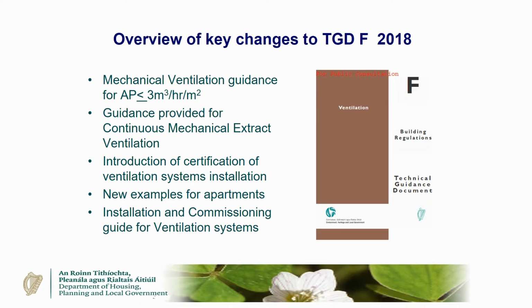We're proposing to introduce a certification scheme for ventilation systems when they're installed. So the installer will install the mechanical ventilation system, he will commission it, and then we'll have a third party, like possibly the air tightness testers, or a scheme running in parallel with the air tightness testers, where a competent third party will come in and validate the ventilation flow rates for the systems that are installed to TGDF. We've added some examples for apartments, and we've also produced an installation and commissioning guide for ventilation systems to tell the installers how to install and commission those systems.